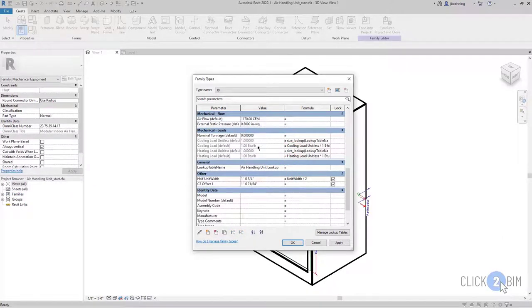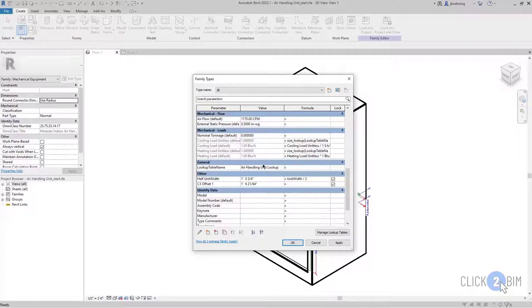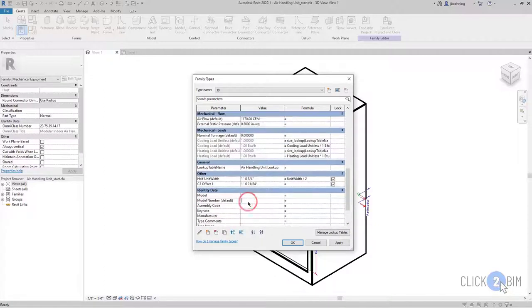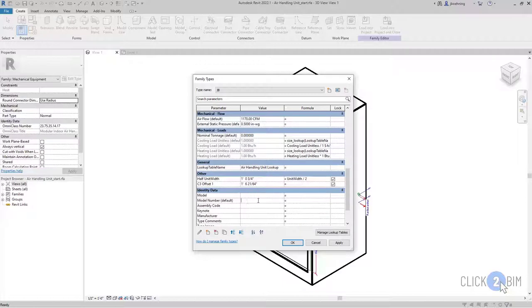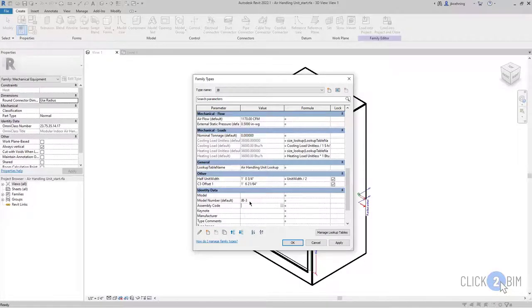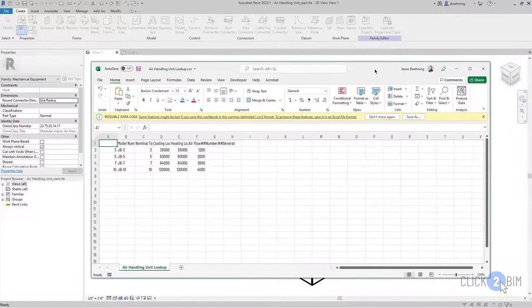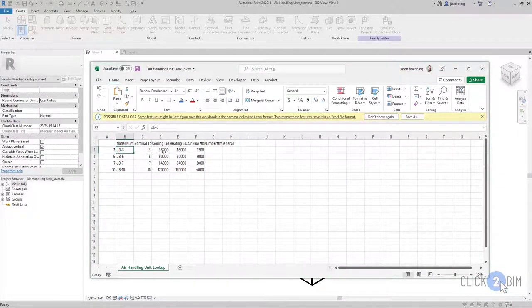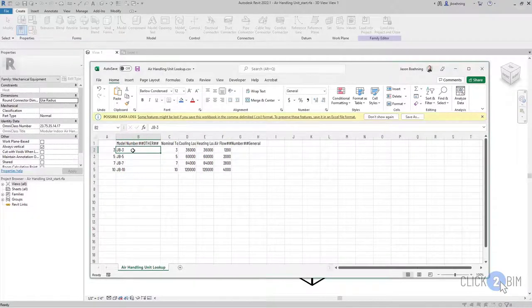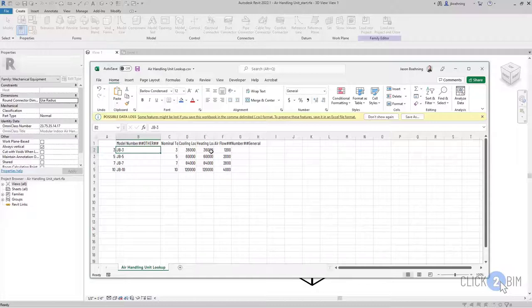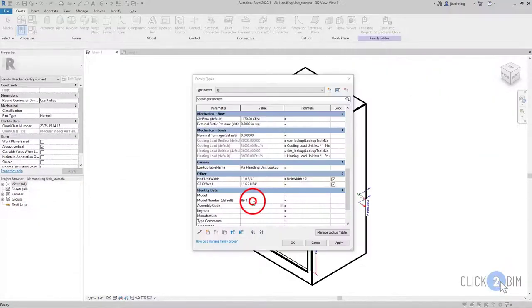Okay, so now we're getting a one here just because we're missing the model number there. Now, if I change the model number, which is what we're basing the lookup function off of, and I change that to JB-3, which let's just take a look here and double check. So if I change the model number to JB-3, then my cooling load and heating load should each be 36,000, because we're telling Revit to go look for this value, which is JB-3. So then it's looking in these columns because that's what we defined in the size lookup function. And now if we change it, the model number accordingly, we should see these things update.